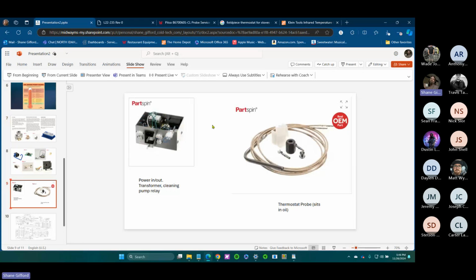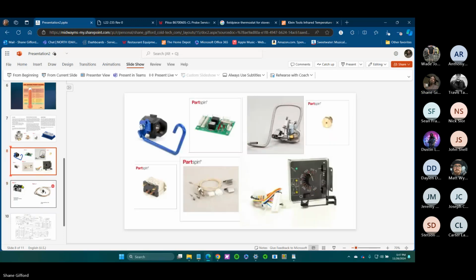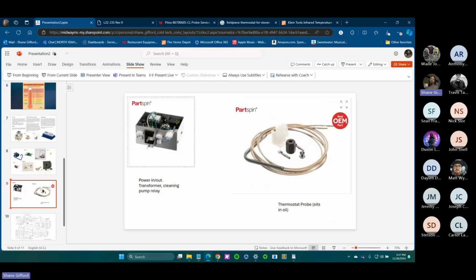This is, again, particular to that one fryer, Pitco. I learned the hard way where this little thing was at. This thing is very hard to get to. It's in the lower front right, and this is where your main power comes in. And then if you've got double fryers next to each other, the left wire coming in is from the wall, but then this right cable, it's a computer cable, hops from this box out and over to the next fryer over and lands in the same location. So that's just a hopscotch point for the 120. But right in here is your pump controls. So your relay, this guy right here, is inside this box. The transformer that produces all the low voltage for the control wiring is inside this box.